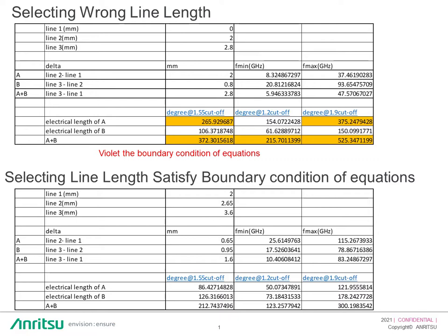If you want to design your own cal kit, you can. For instance, selecting lengths of 2mm, 2.65mm, and 3.6mm — you can see the electrical length of A, electrical length of B, and A plus B all satisfy the boundary conditions of the equations.